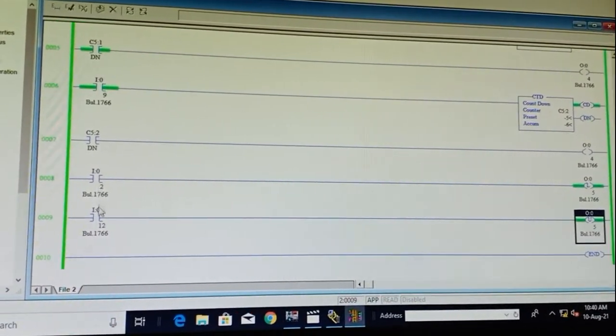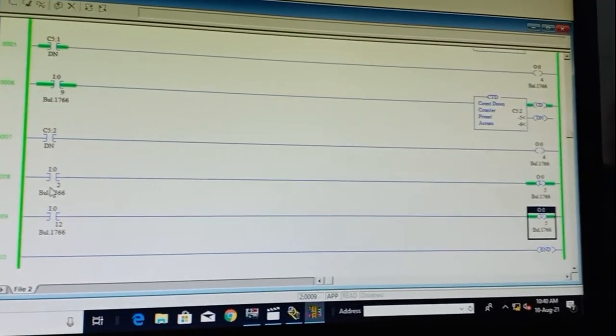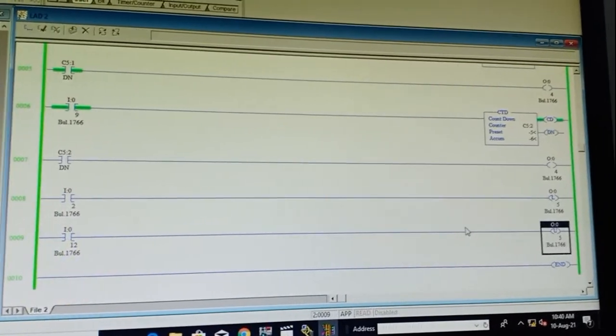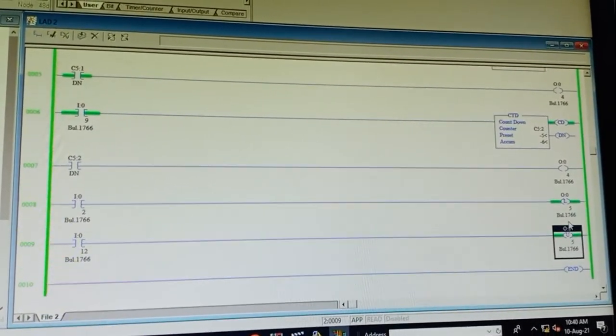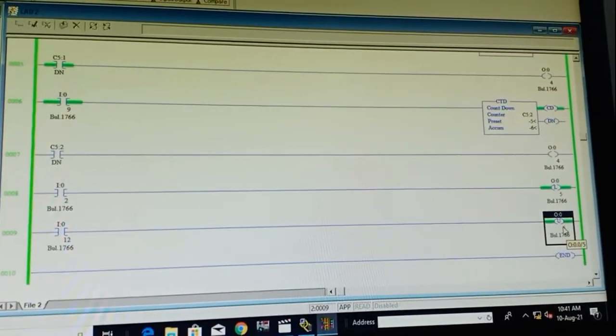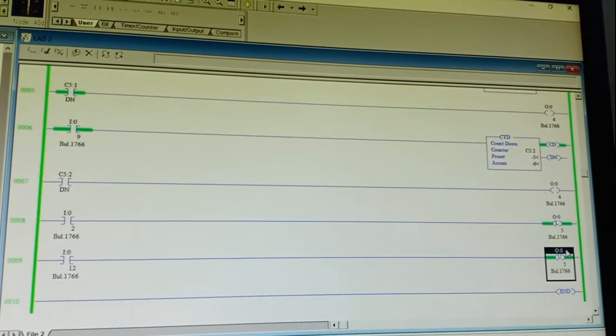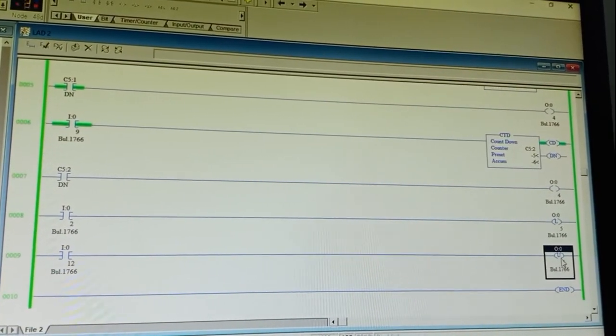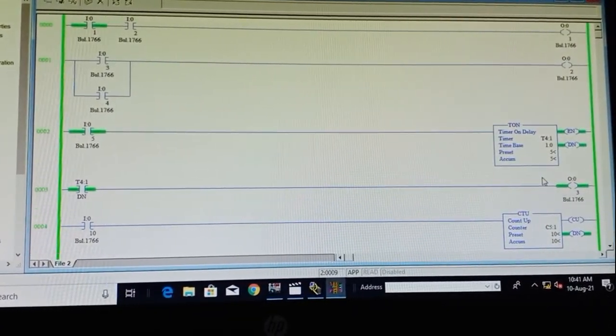The input address is I2 (second input) and the 12th toggle bit for unlatch. Rahul presses the second input — as soon as pressed, motor is in latch condition, latching starts, motor is on. When Rahul presses I2 again, the motor will not turn off because it is latched. To stop the motor, press I12 to unlatch. As soon as I12 is pressed, motor becomes unlatched and turns off.